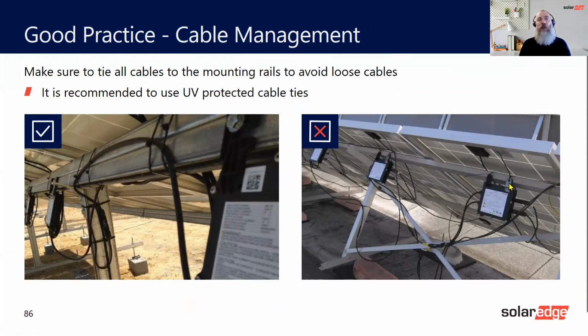What will happen is that the cable insulation will break. You can see on here, this one is pulled right round as well. So be careful how you connect them. We don't want any stress or strain on the connections. Otherwise, you'll get an issue with insulation resistance, with ground fault issues as well. And they can be attributed to the cable itself chafing, the cable being stretched, as you can see on here. So stretched, connectors not connected in the right manner, and things like that. So please be careful with how you connect stuff. Cable ties are okay, but they're not going to last forever, so you can use metal cable ties. This just stops the cables from moving.